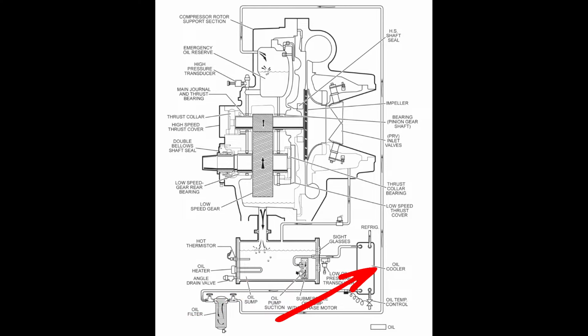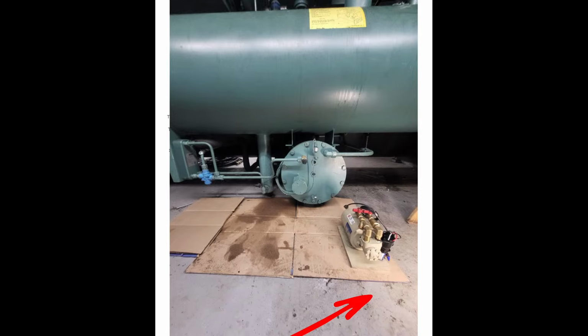Then we come into our oil heater itself. Is the oil heater functioning correctly? One of the ways I'm looking at that is, okay, so we've got our metering valve coming in. So if we come back to this photo, we can see that right here. So this is our oil cooler. This is the metering valve. This valve is going to have a sensor on the leaving side. Actually, hang on. That is our oil pressure regulating valve, right? Let me follow this here.